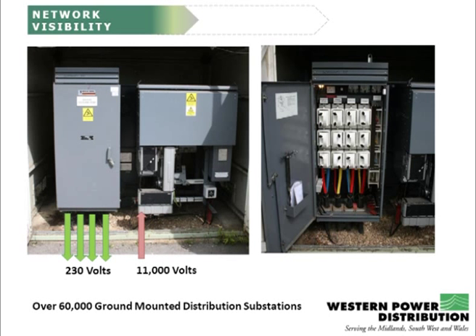On the left-hand side, you've got a cabinet with power flowing out through a number of different cables at 230 volts. It flows in originally through a switch on the right-hand side at 11,000 volts, and at the back of the unit, which you can't see, there'll be a distribution transformer that changes the voltage.